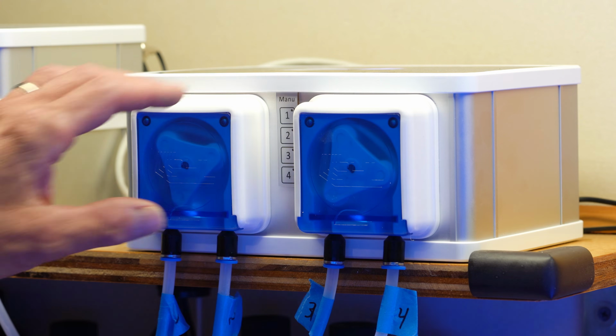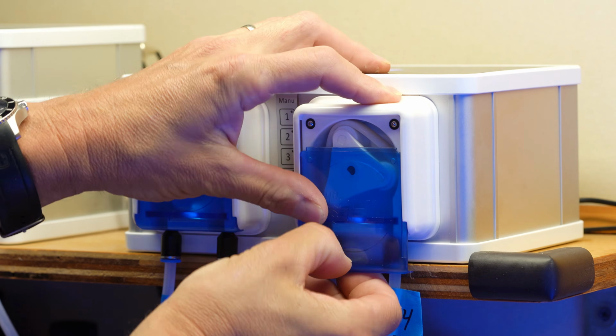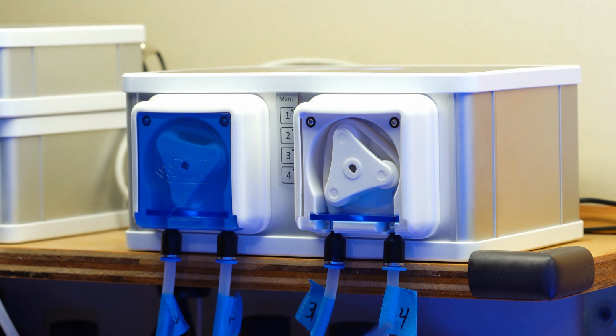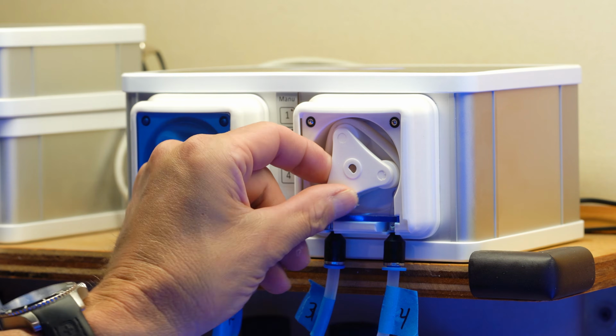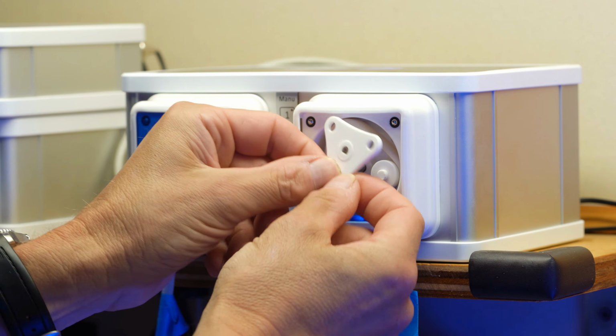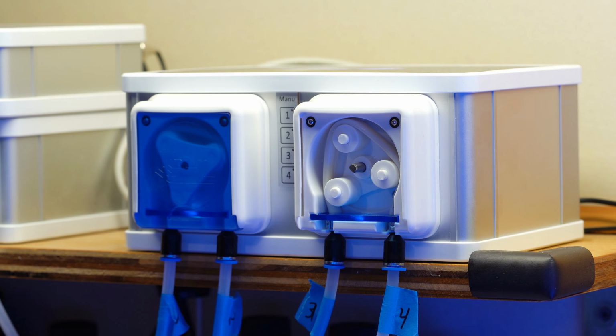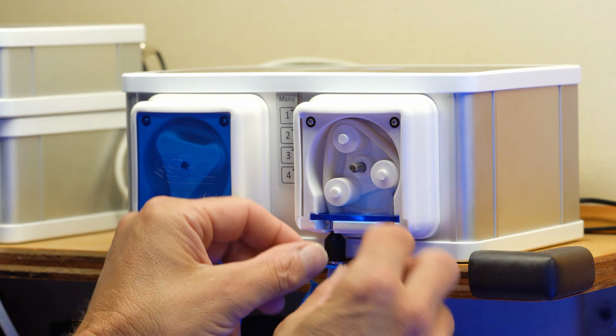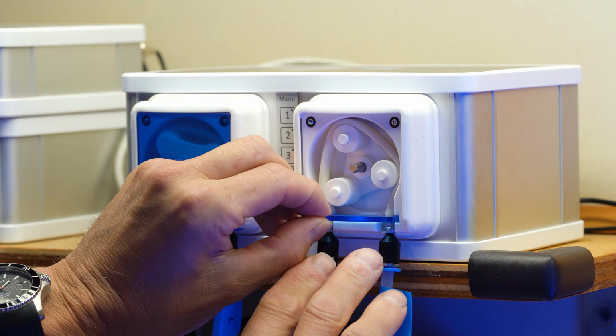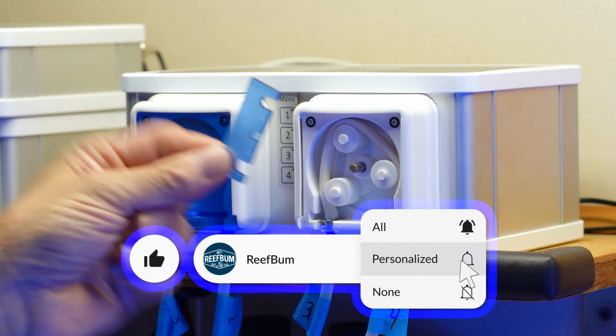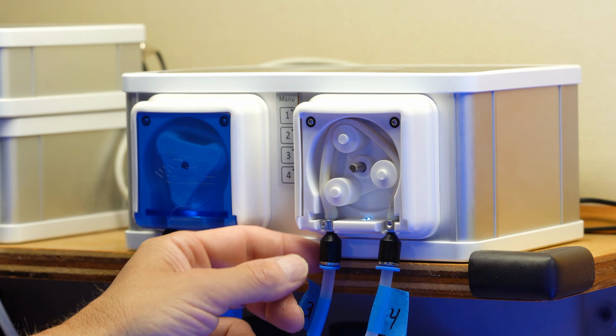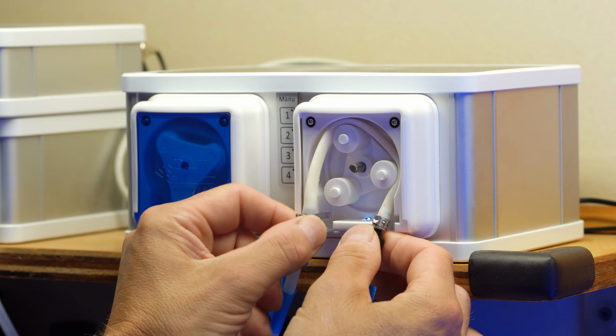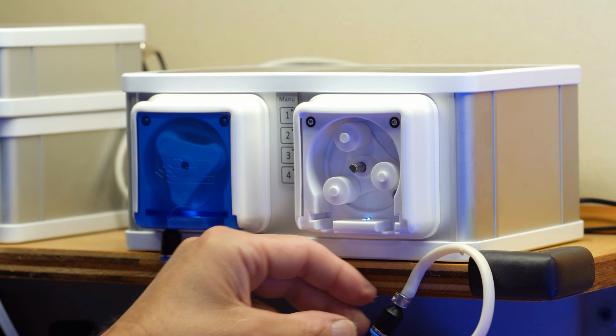For each dosing head, just slide off the cover, which comes off easily. Then disassemble the unit: this plate pops right off, then remove the plate on the bottom that holds the tubing in place, which has a couple of grooves. Removing that allows you to pop out the silicone tubing, which comes out easily.